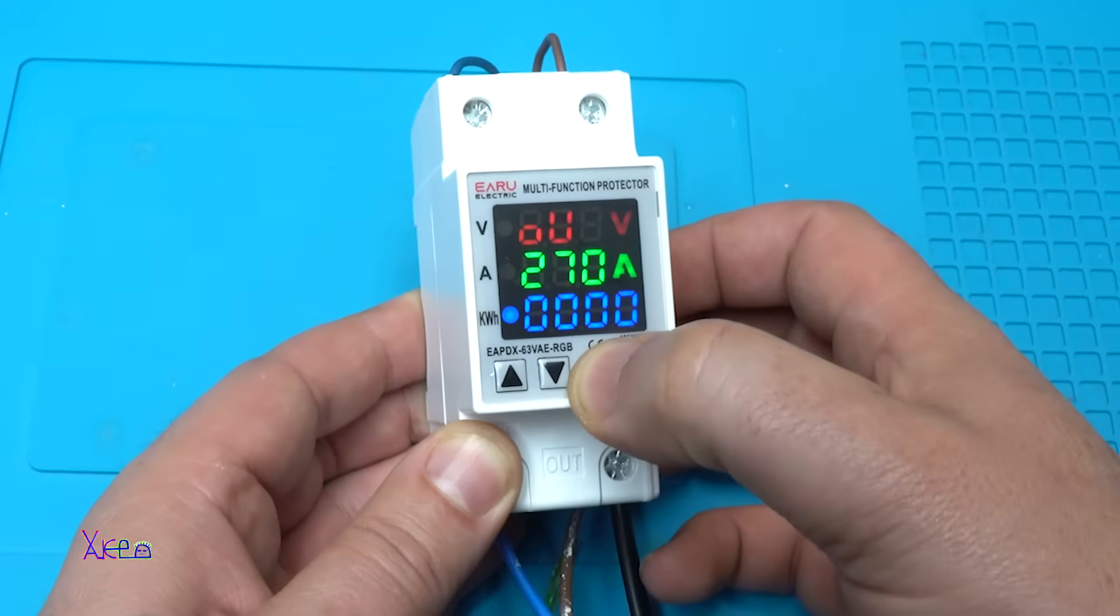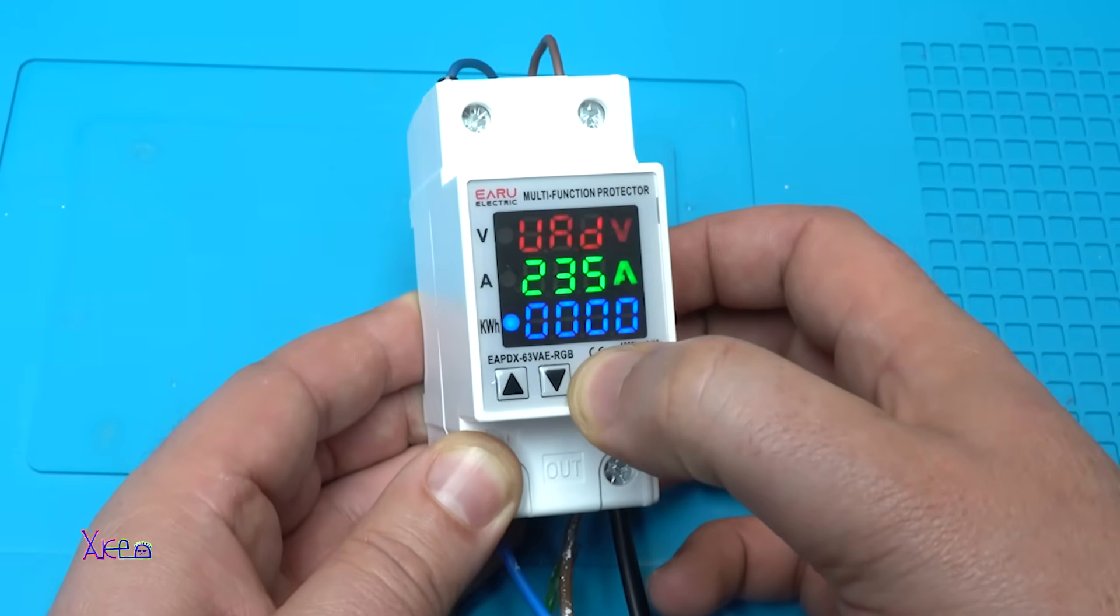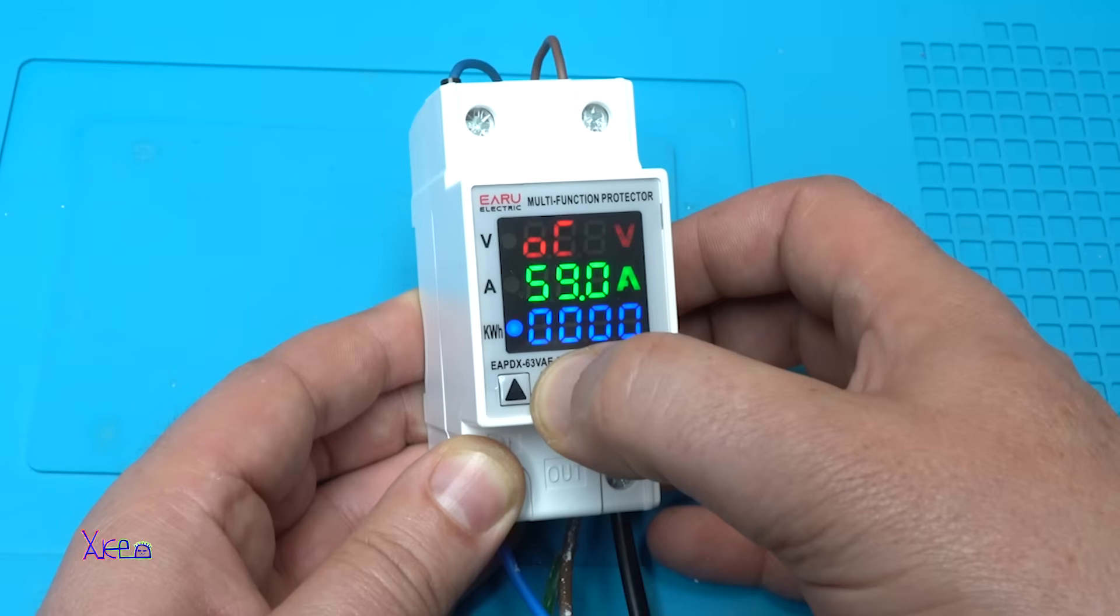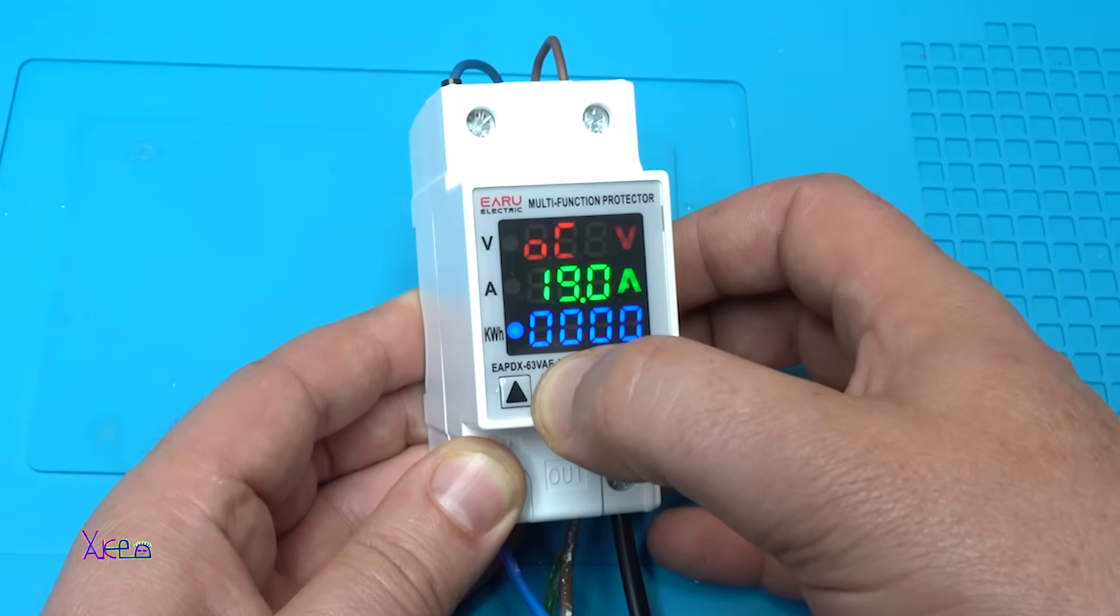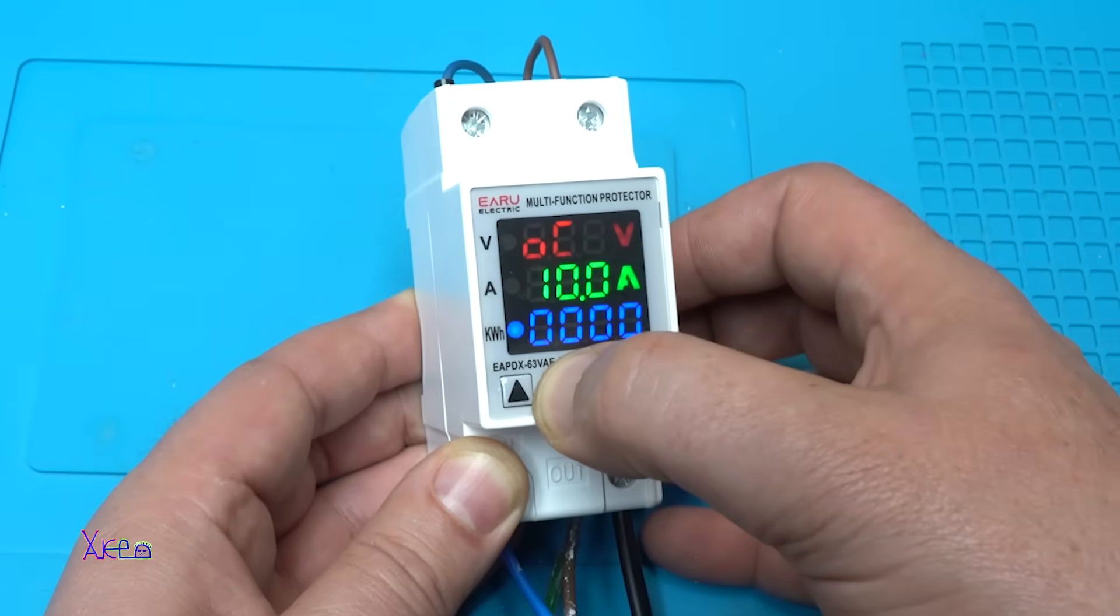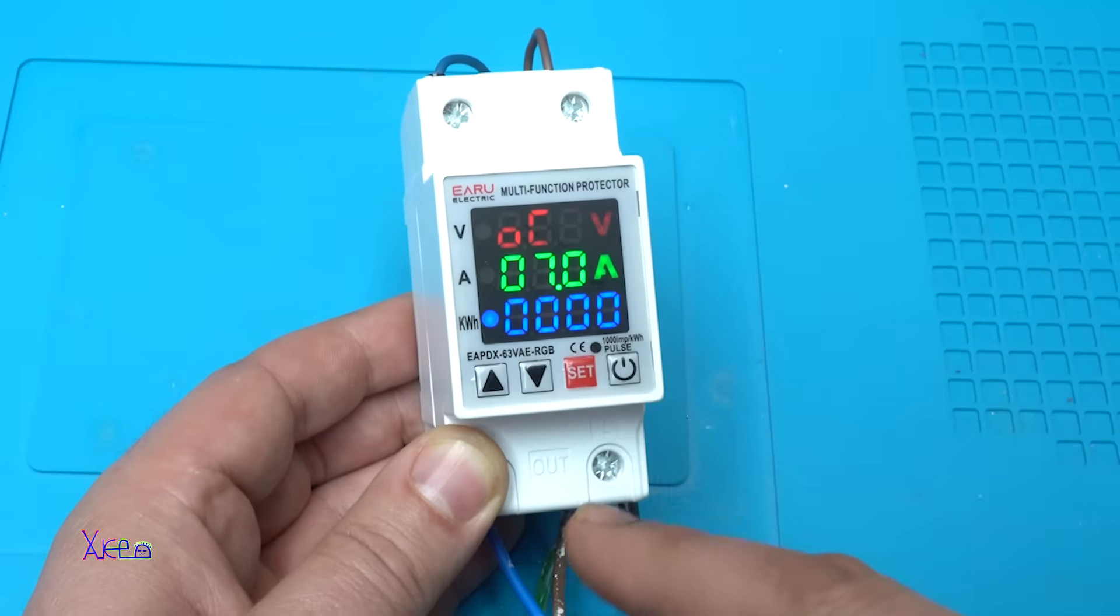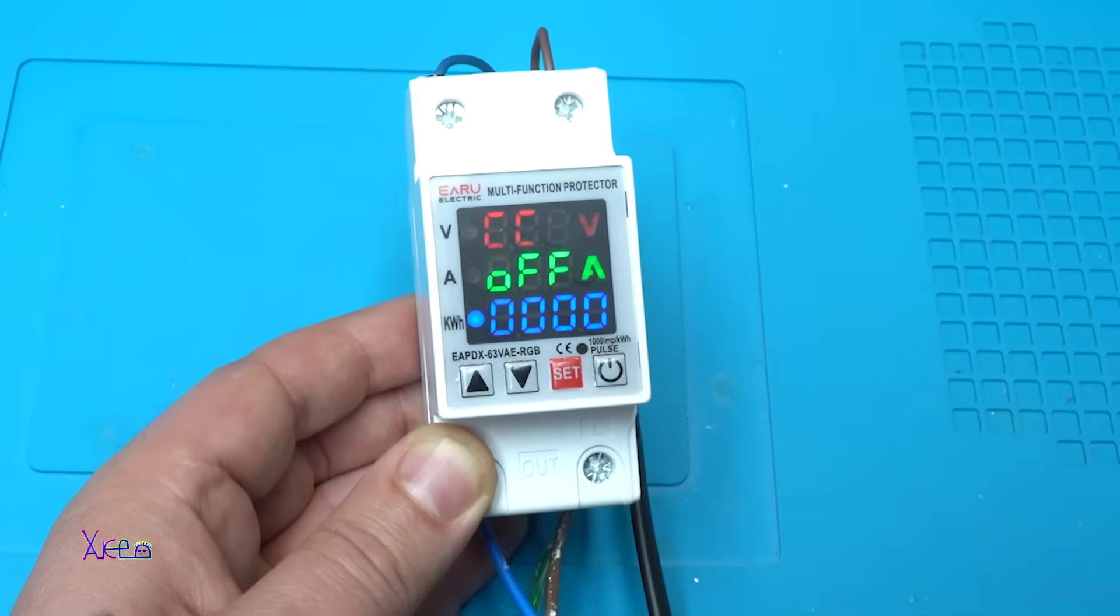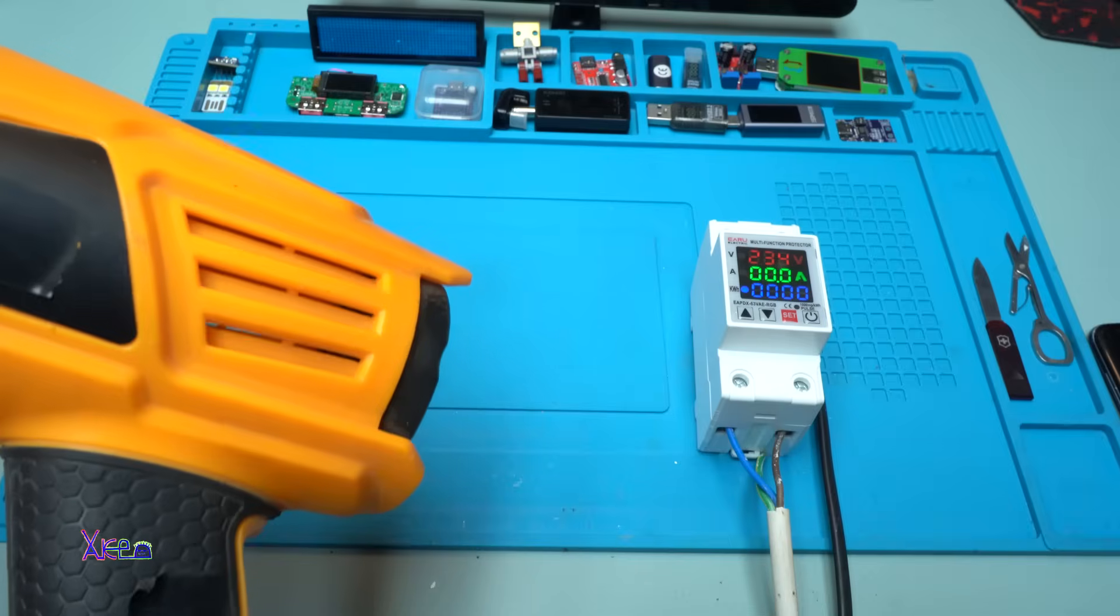Now I'm going to set the over current protection. And it says OC. And it's set on 63 amperes. I'm going to adjust that to 7 amperes. That is the current that I want to show you something. Yes. 7 amperes. Leave it like this. Or just go to the next settings. And you will go out of the menu. Or hold the power button. Yes. Okay.